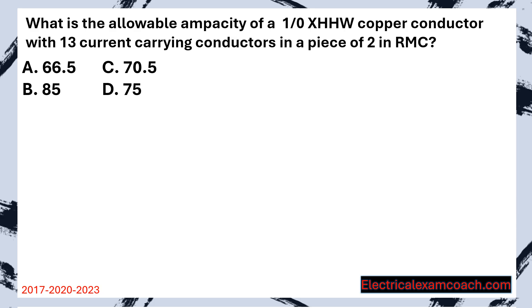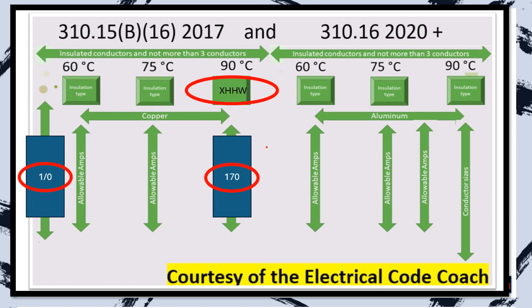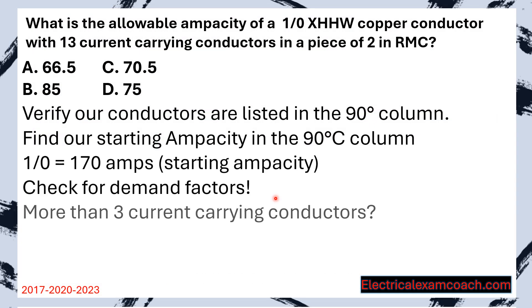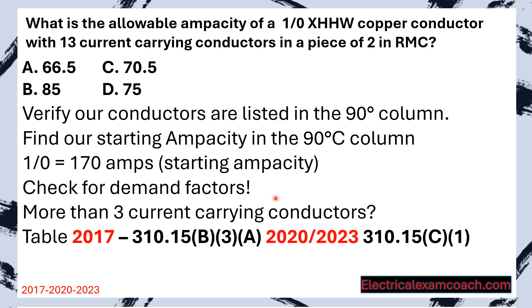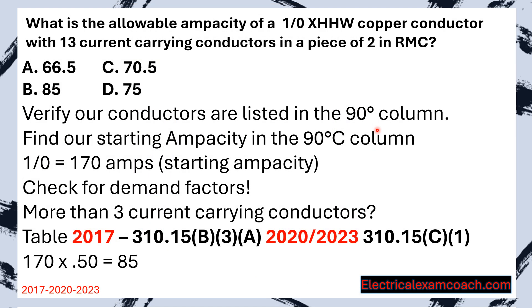Practice question: What is the allowable ampacity of a 1-0 XHHW copper conductor with 13 current carrying conductors in a piece of 2-inch RMC? Step one: verify XHHW is listed in the 90°C column — it is. Step two: on the copper side of the primary ampacity table, find 1-0 and cross to the 90°C column — starting ampacity is 170 amps. Step three: more than three current carrying conductors, so apply the adjustment factor from the table — 50%. Taking 170 amps multiplied by 0.50 gives a new reduced ampacity of 85 amps.